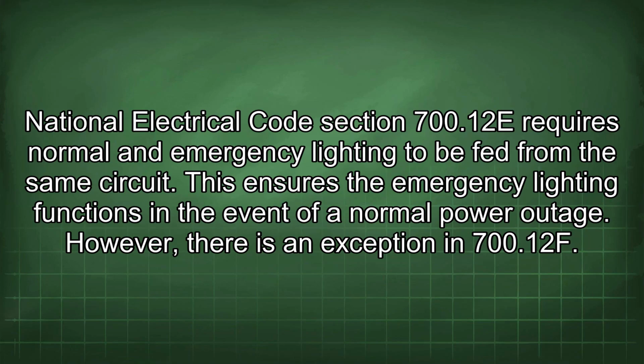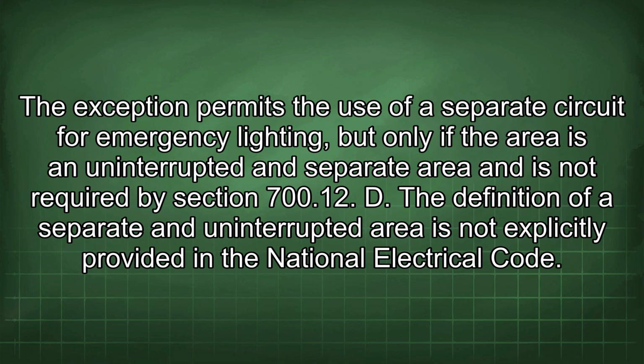National Electrical Code Section 700.12(e) requires normal and emergency lighting to be fed from the same circuit. This ensures the emergency lighting functions in the event of a normal power outage. However, there is an exception in 700.12(f). The exception permits the use of a separate circuit for emergency lighting, but only if the area is an uninterrupted and separate area and is not required by Section 700.12(d).